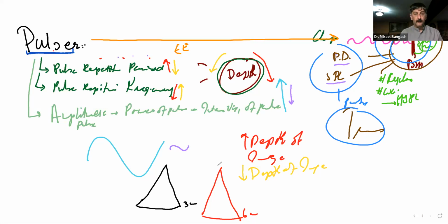Whereas we may decrease the image back to, let's say, just 2 centimeters, for instance. So that becomes the depth of our image, and we tell the system this is our depth. Now it doesn't need 39 microseconds between each pulse to go and come back. It's good with just 26 microseconds of a pulse repetition period. But that's going to be an equal and opposite increase in the frequency.